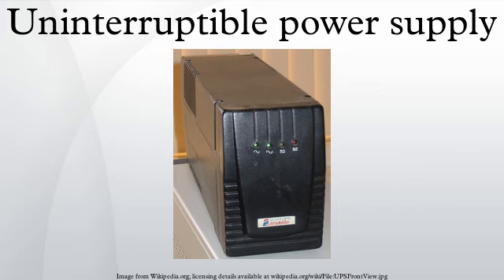This once was the dominant type of UPS and is limited to around the 150 kVA range. These units are still mainly used in some industrial settings due to the robust nature of the UPS. Many ferroresonant UPSs utilizing controlled ferro technology may not interact with power factor correcting equipment.